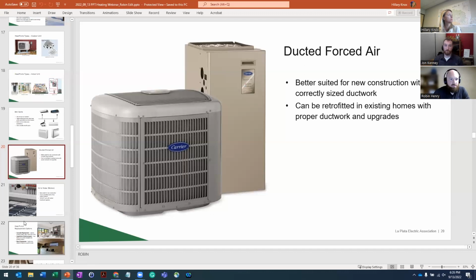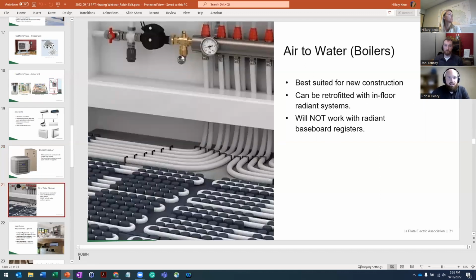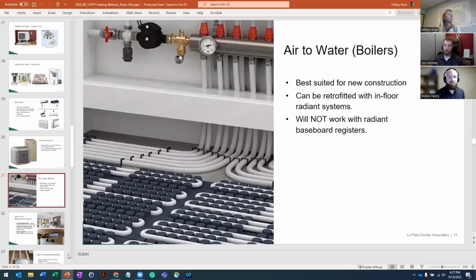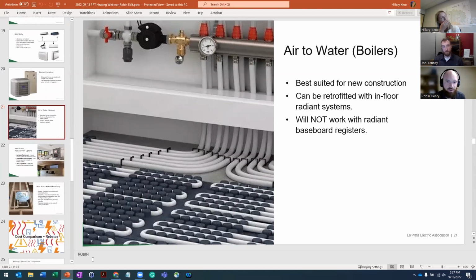Next slide, please. Again, the hydronic boiler, air to water application. You can see here it's a little overkill, but honestly, that's what they're going for, compared to your traditional in-floor system where the loops are 8 inches or so apart. These guys are half that, or even more so, with how the loops are spread. The heat coming out of the heat pump boilers is 120 to 130 degrees, so in order to deliver that heat, you need tighter loops to get that heat where you need it. So nothing that can't be done, just some design considerations and new tech coming online.